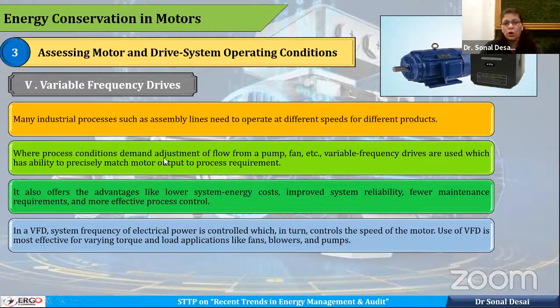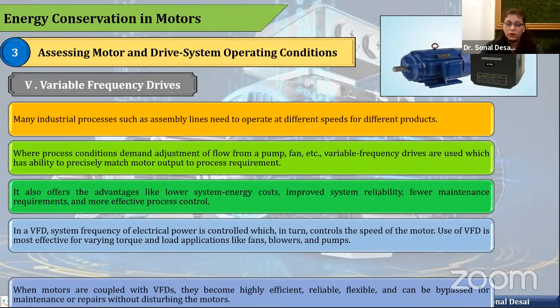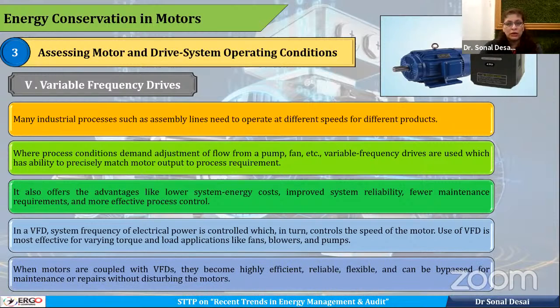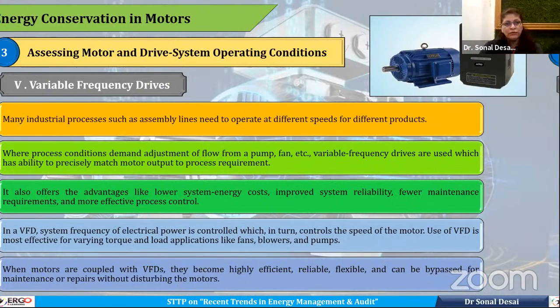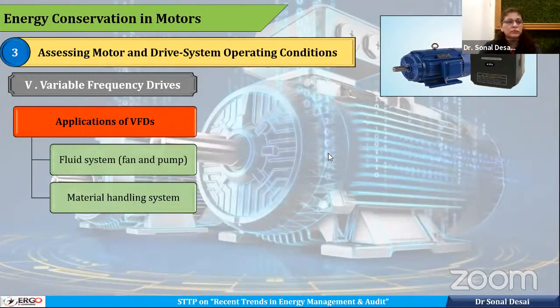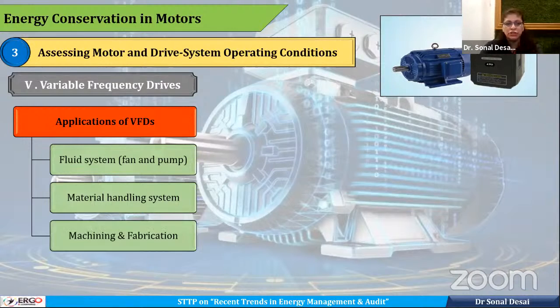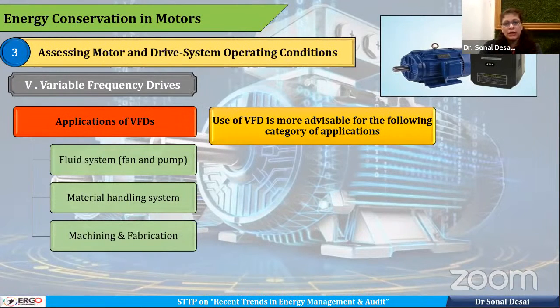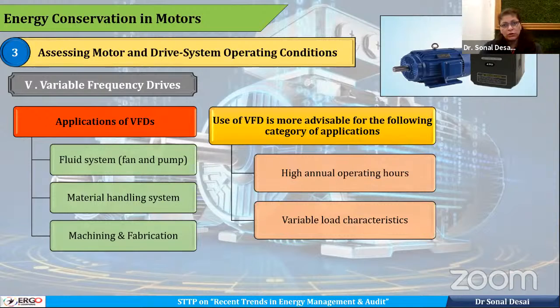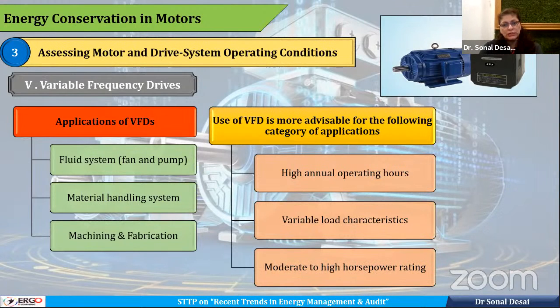So it is most effective for varying torque and load application, in particular for fan, blower, and pump, also for compressor. So they are reliable, they are flexible, and they will reduce the maintenance of the system. Variable frequency drive applications are used for fan and pump. They can be used in material handling, machining and fabrication. And they are more advisable where there are high annual operating hours or a variable load characteristic, and a moderate to high rating of the system. Over there, use is advisable.